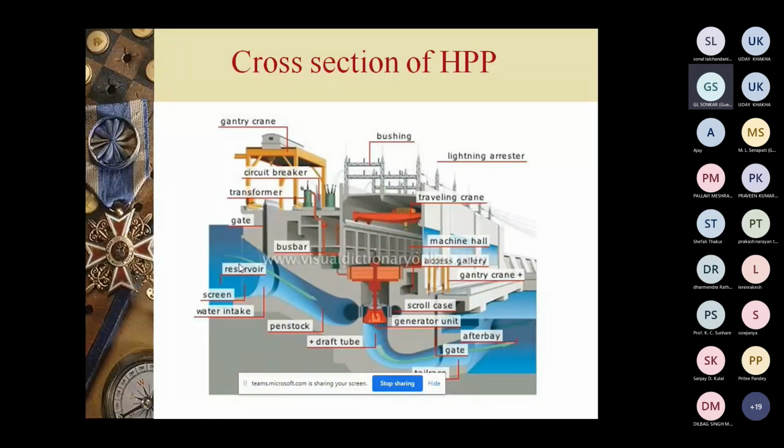Then you see after the intake, you have the turbine. Then you can see the draft tube. This is called a penstock, what is studied at our postgraduate or graduate level. This is the penstock, but we people call it the pressure shaft, because as I discussed, the HRT part is slightly slanting, but the pressure shaft is heavily slanted. That means the pressure in that particular patch of the water conductor system is high. So you have to concentrate on the material as well as the thickness of the pressure shaft rather than the HRT.